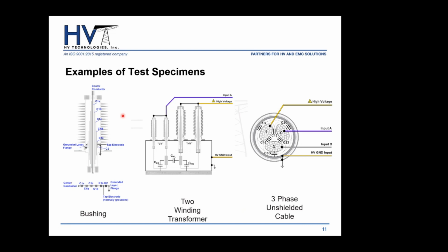For example, in a capacitive graded bushing, you have a center conductor, and then you have layers of oil impregnated paper, and this is built up, and so you'll have a series of capacitances that will make up the total capacitance of a bushing. And then you also have a capacitive element when it comes to your bushing tap. So in a bushing, you'll have two different types of capacitances that you will usually measure. On a two-winding transformer, for example, you have your high voltage winding and a low voltage winding. This is a very typical application.